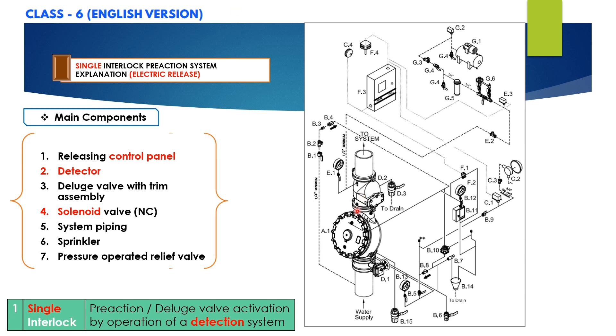The deluge valve can only be reset after the system has been taken out of service and the outlet chamber of the deluge valve and all associated trim piping are depressurized and drained. For example, if any sprinkler opens prior to operation of the detection system, or if supervisory pressure in the sprinkler piping is lost, the air supervisory switch E3 will signal a low air pressure condition in the releasing control panel, but the deluge valve will not open. If the detection system operates due to mechanical damage or malfunction, the deluge valve will open, but water will be contained in the sprinkler piping until the sprinklers are activated; the water motor alarm and alarms connected to the alarm pressure switches will activate.